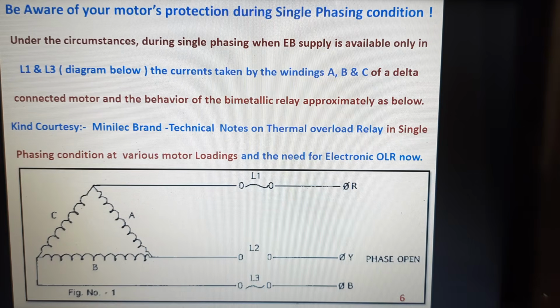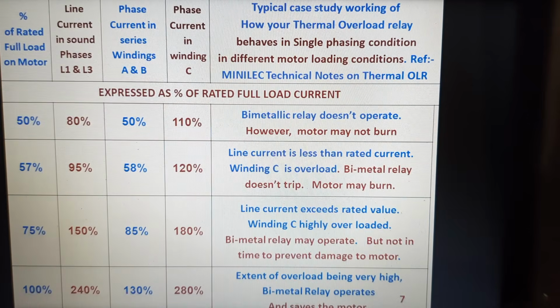The behavior of the thermal OLR, how it is happening here. Kind courtesy of the Minilec brand technical notes on the thermal overload relay. It is an excellent case study on the thermal overload relay, and each and every industry needs to go through this case study. You can see, for the given percentage of rated full load current, all are expressed in terms of percentage of the rated full load current at 50%, 57%, 75% and 100%. You can see the line current in the phases L1 and L3, the phase current in the windings A, B, and the phase current in the winding C.